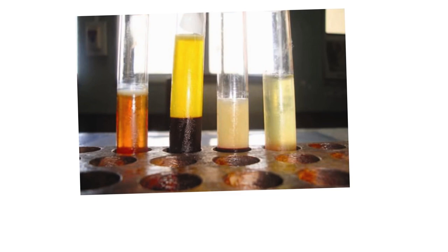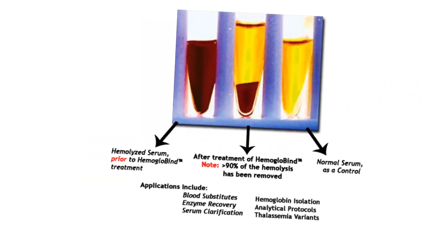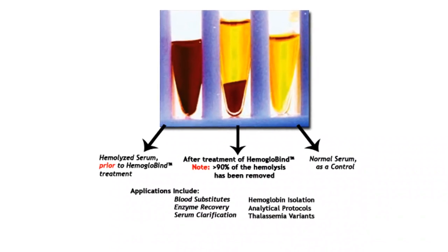This image compares normal serum on the right tube — serum that has been removed from the blood collection tube to show normal appearance. On the far left, this sample is hemolyzed so badly that the serum is very red. The middle image is showing a product where you put it in a heavily hemolyzed sample like that, spin it, and all the hemoglobin goes to the bottom so you can recover some normal-looking serum.